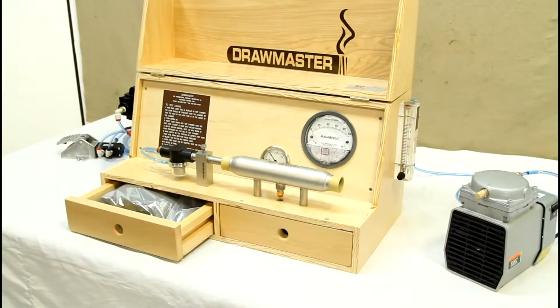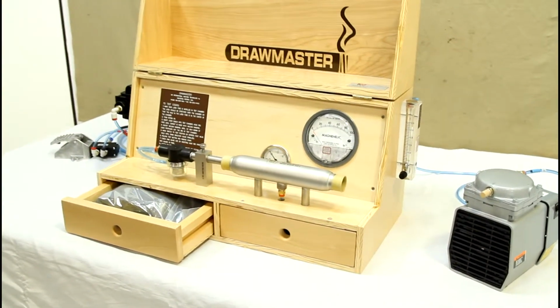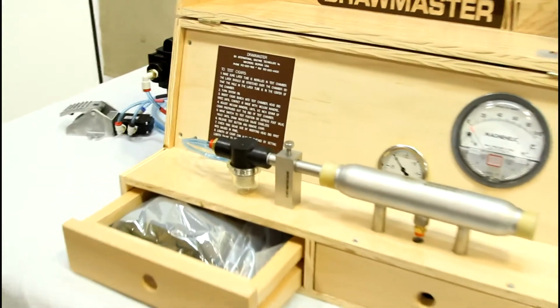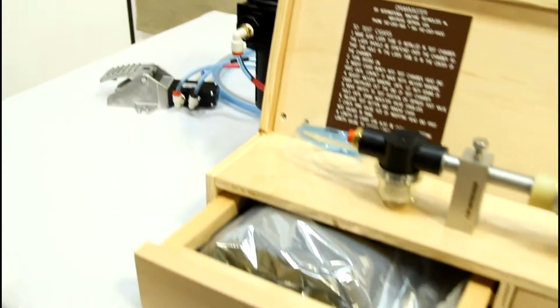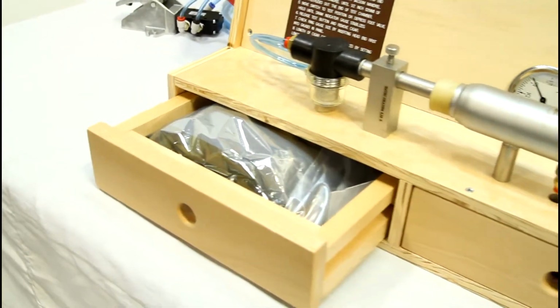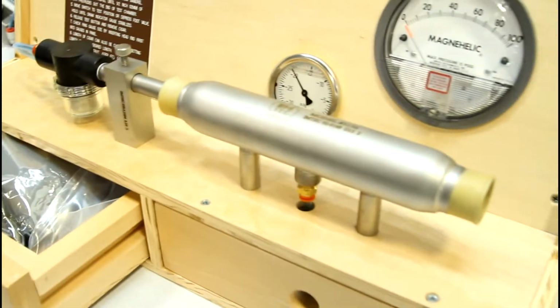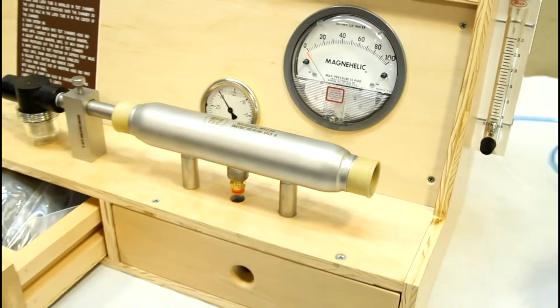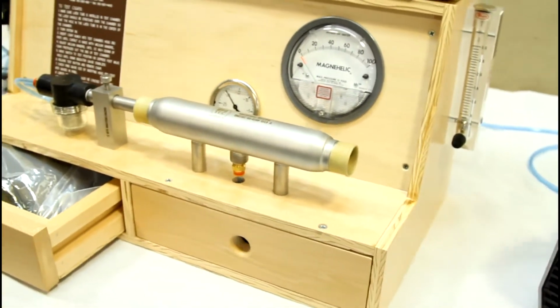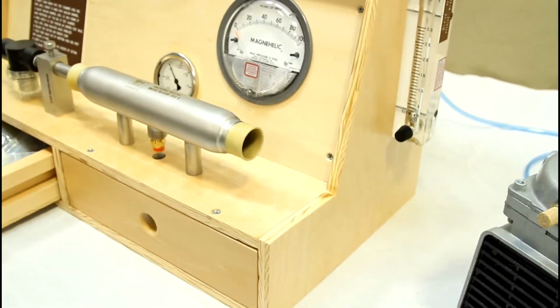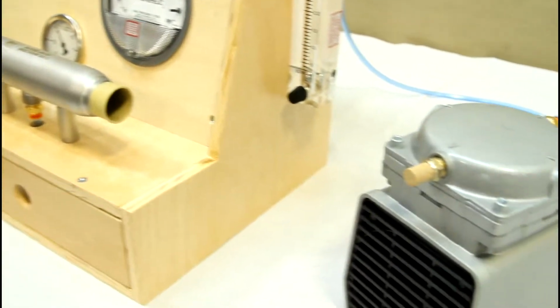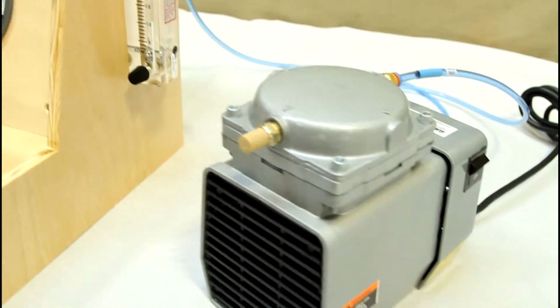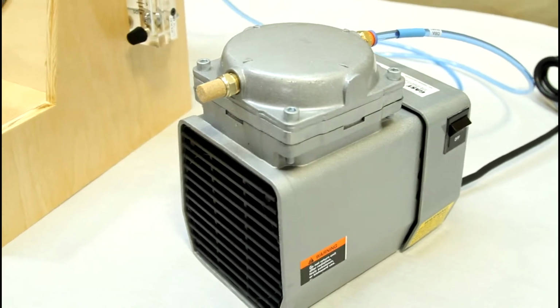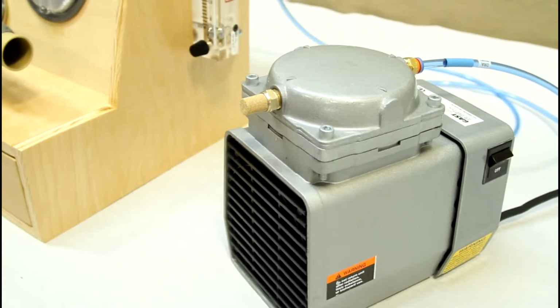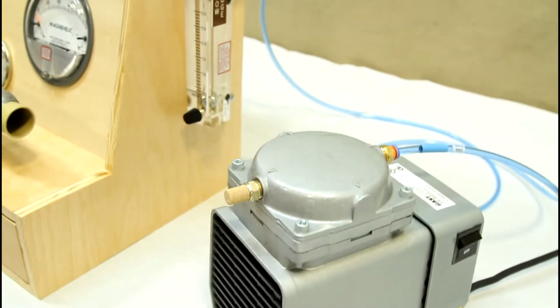Your daily maintenance checklist should be to clean the primary filter, the secondary filter, inspect your latex for pinholes or tears, keep them out of the direct sunlight, preferably in the drawer in the bag that it is put in. Keep the vacuum pump clean of debris, and make sure that the hoses have no holes or tears.